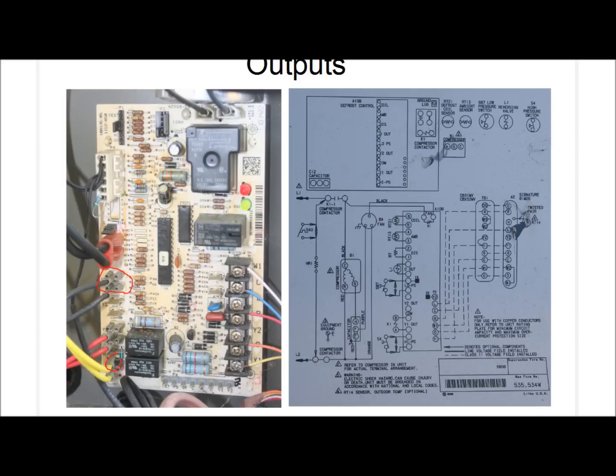These just are safety controls, and let's look at the schematic over here quickly. When we have a 24 volt signal coming in on the Y terminal, I know I said it went to the Y out, but what it does is it goes through the high pressure switch and looks to see if there's a high pressure fault. If there isn't, it goes right back in through the control board. Then it looks for a low pressure fault on the low pressure control, and then it finds its way back out to energize the contactor. All right, so these are your high and low pressure controls to indicate if there's a fault. What those do is it will not allow that heat pump to turn on if there's a high or low pressure fault. We'll talk more about that a little bit later, when we get into the troubleshooting portion of this.